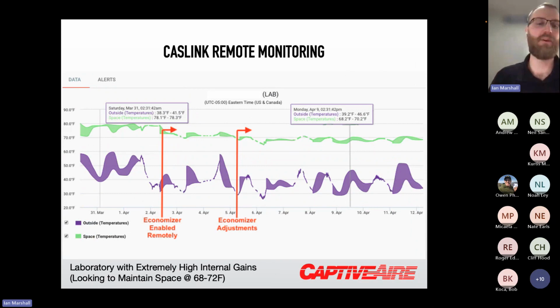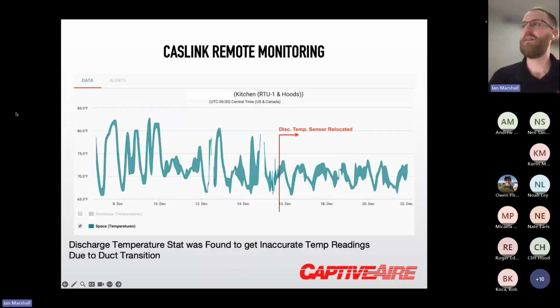This one was a lab that had a lot of high internal gains, and we were able to essentially make some economizer settings changes remotely that were able to bring the temperature of the lab down. So we were able to bring in more outdoor air ventilation into that space over the course of a few days and drop the temperature of that lab because of that.